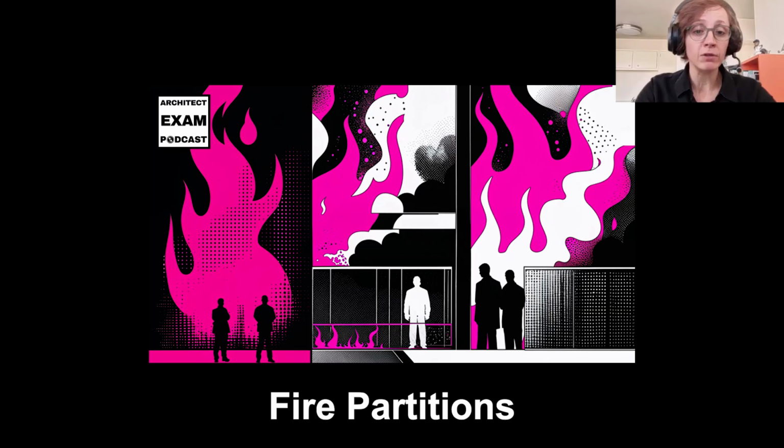In terms of fire resistance ratings, typically for a fire partition, you're going to see a 1 hour rating. And you can terminate the fire partition up to the ceiling. Again, we're starting to go from the most stringent to the least stringent. So with a fire partition, when you think about corridors, that wall doesn't have to go all the way up to the deck.